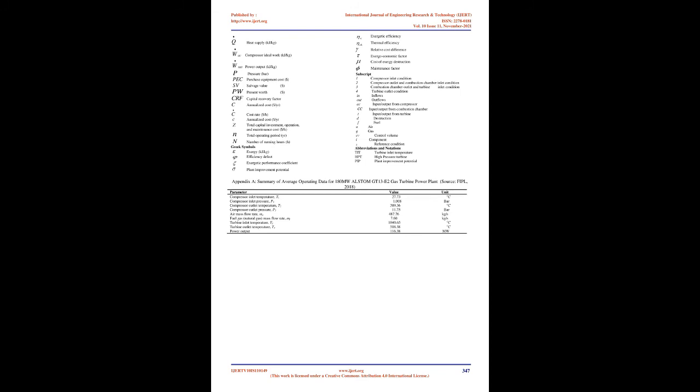79.15%, and 10.46% of the total exergy destroyed, respectively. The air compressor has the highest capital investment, operation, and maintenance costs, an Exergo-Economic factor, F. The overall cost effectiveness of the plant, according to Bejan et al. 1996, is determined by the capital investment, operation, and maintenance costs of the air compressor, which can be reduced by lowering the pressure ratio and/or compressor isentropic efficiency.